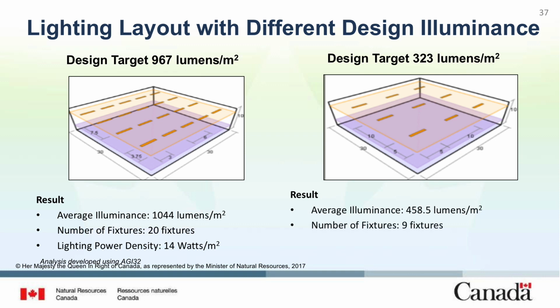Here, for example, you can see that the facility has gone from 20 fixtures on the left to 9 fixtures on the right just by setting an appropriate illuminance target and putting in a more efficient lighting fixture system. This allows the building to hit a lower threshold for power density, that is watts per square meter. That's what you want to do: redesign the space, get in the appropriate light fixtures, and then layer those with appropriate daylighting controls, occupancy sensor controls, and vacancy sensor controls.